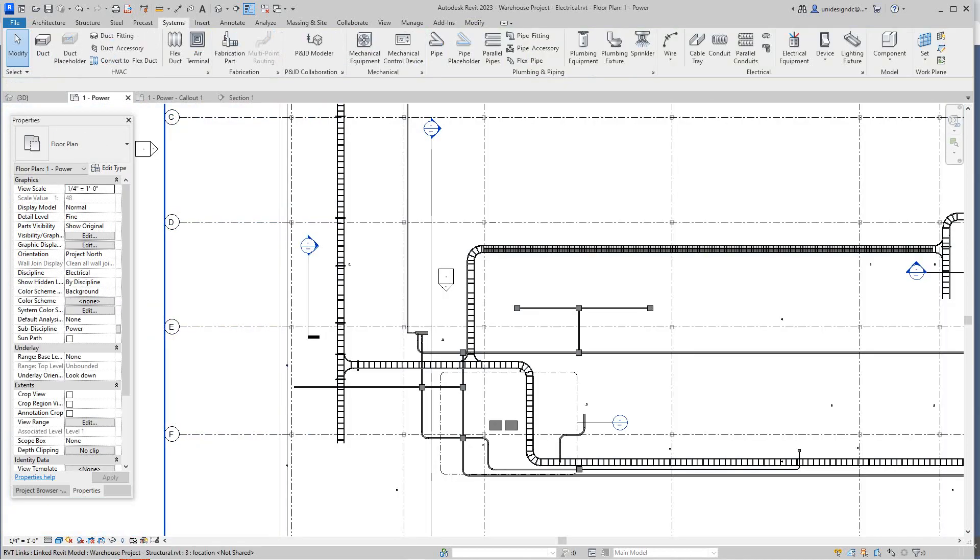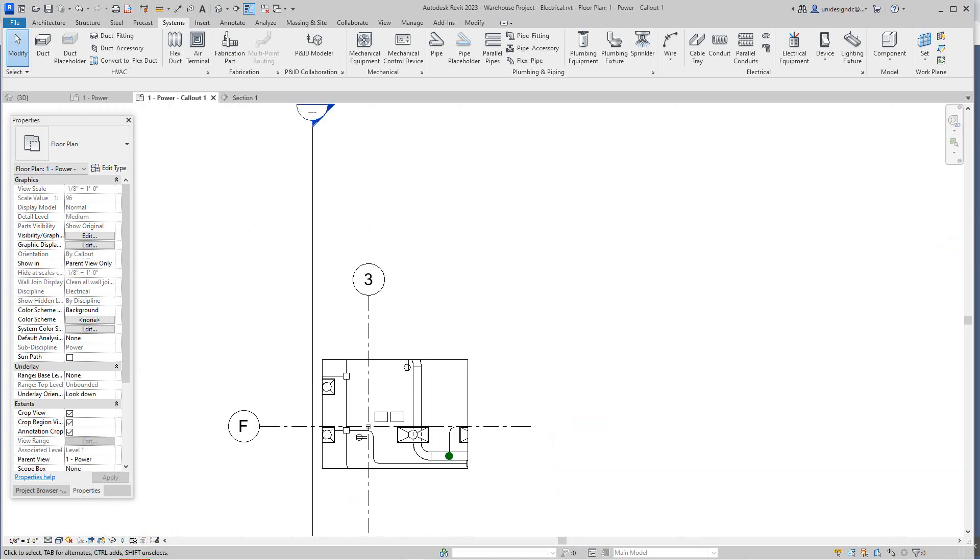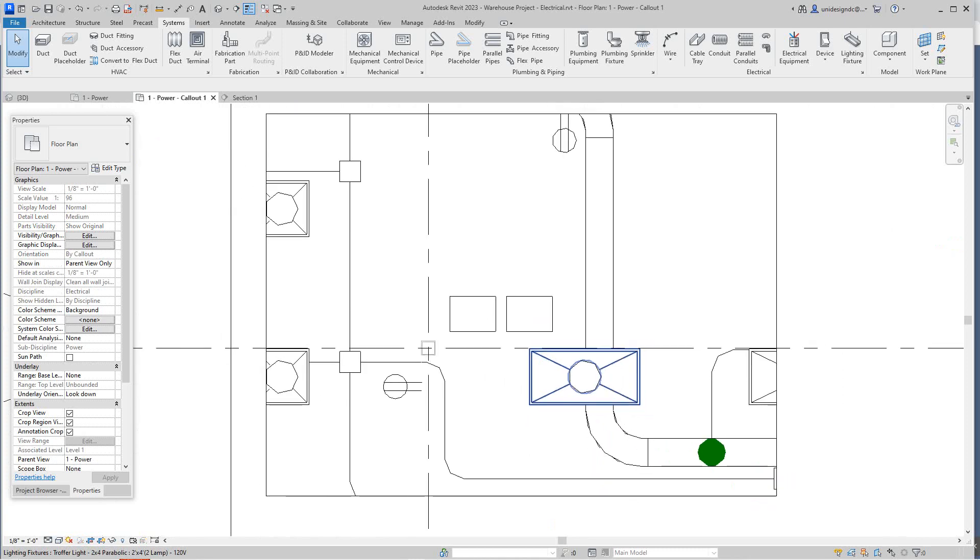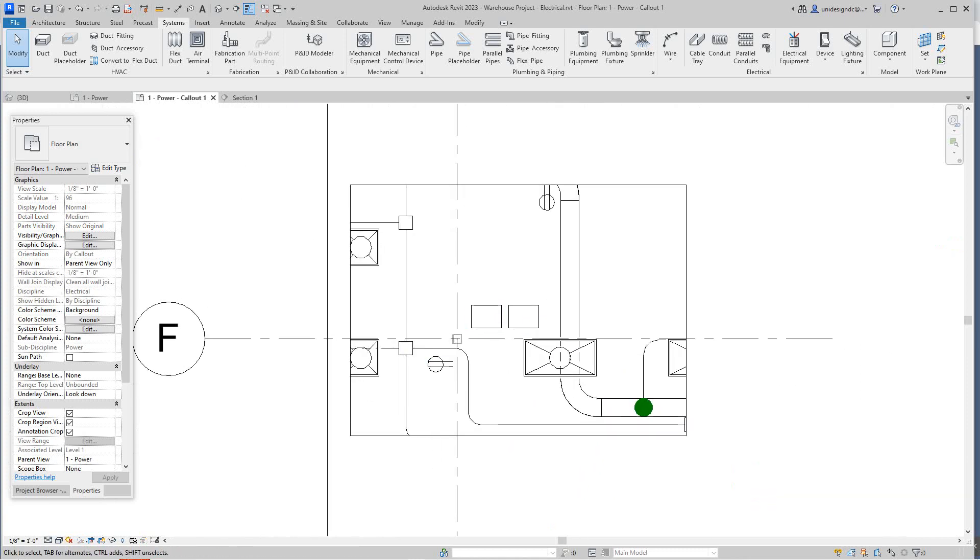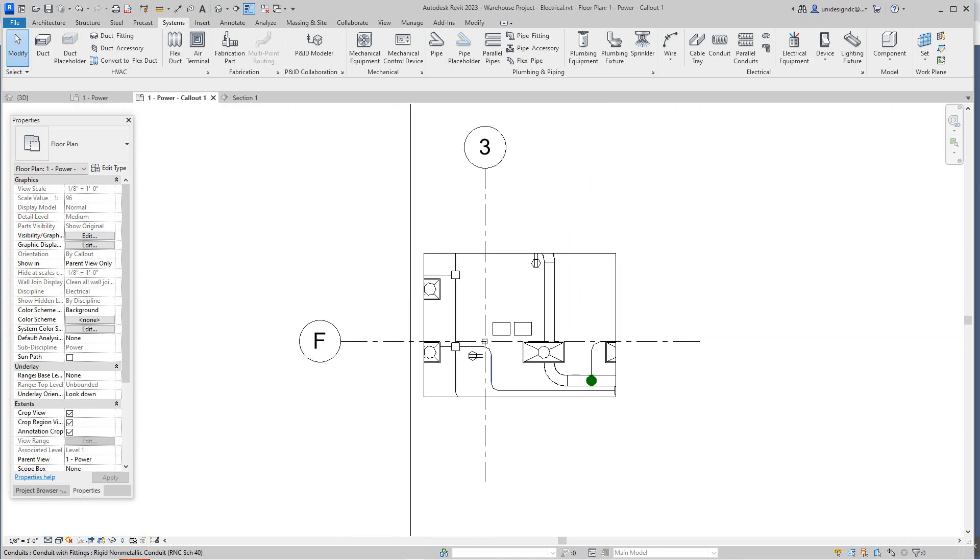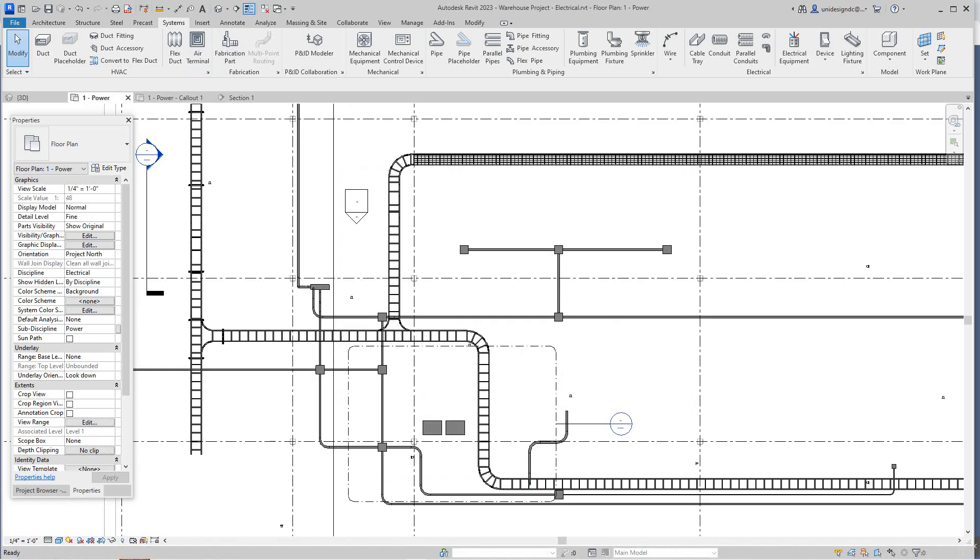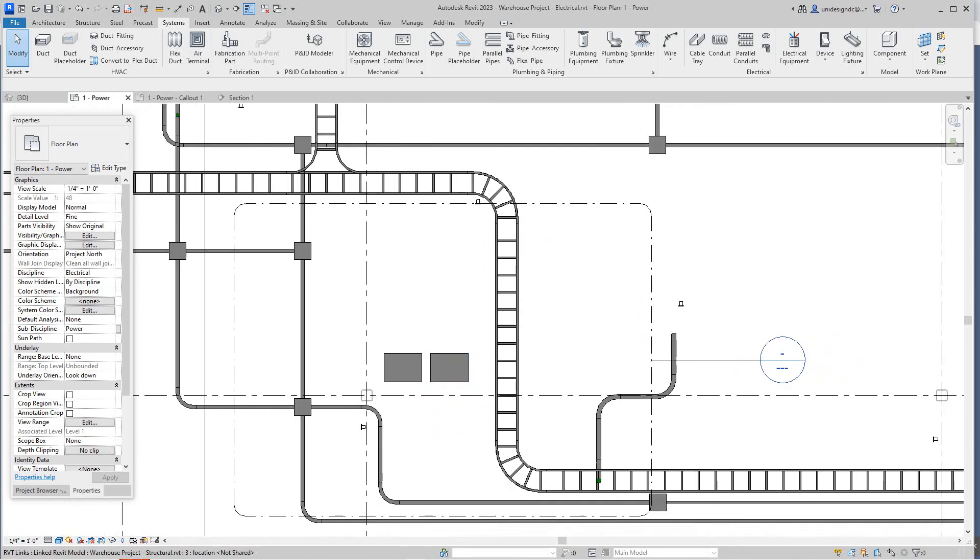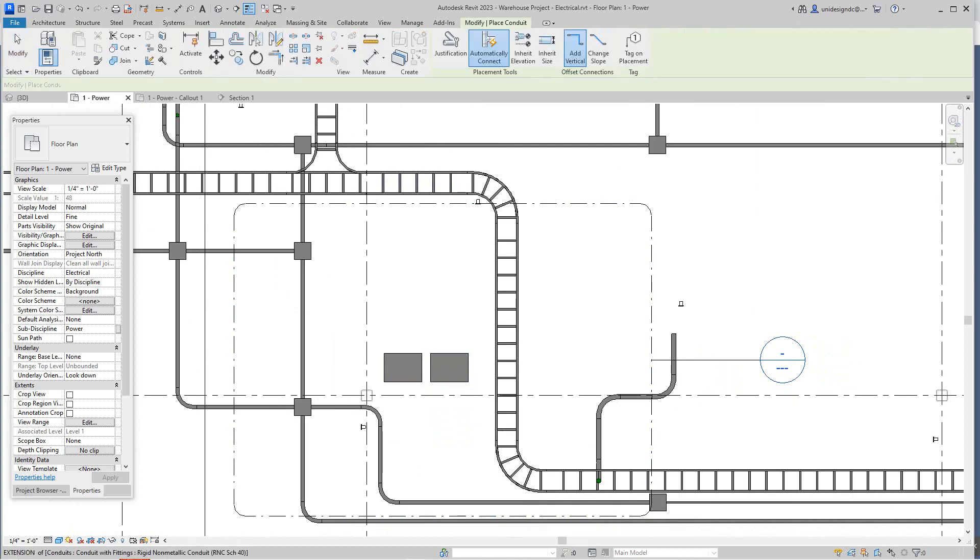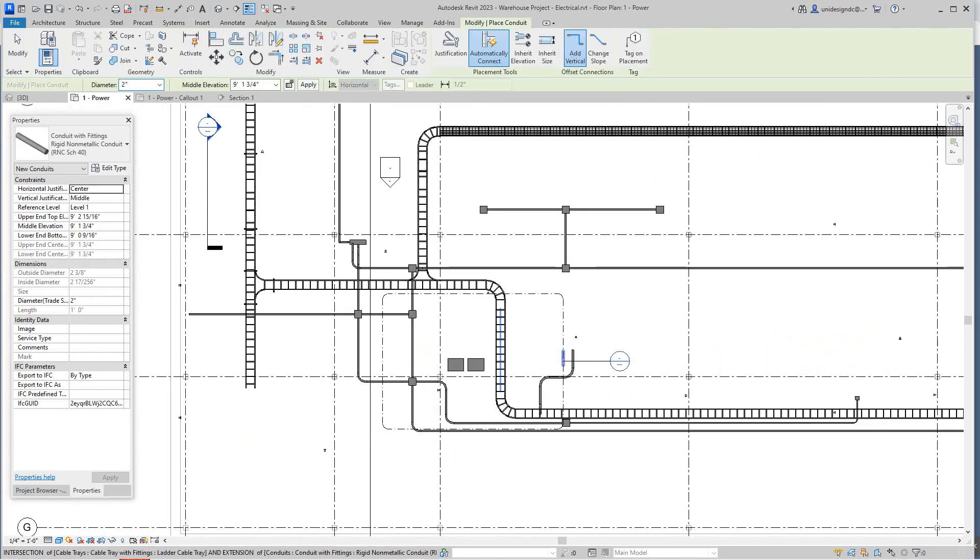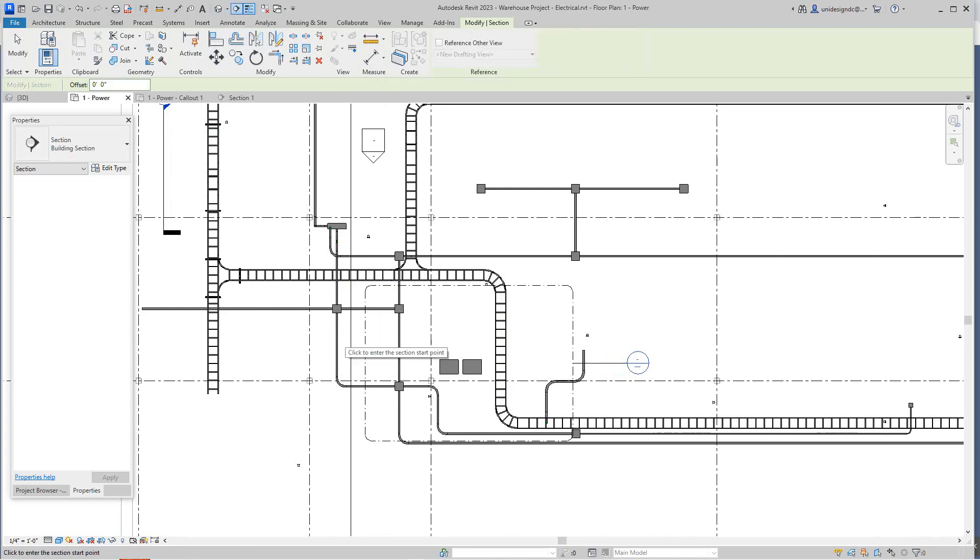So now I'm going to click on this and I got a partial plan of that room with the light fixtures showing and everything. There's a view template going on here. So what I'm going to do, I'm going to back out of this, go back to my power plan and just show you how this works. Basically you go into your systems and then you go conduit. I kind of like to do this in a section view. So let's just drop a section in here.